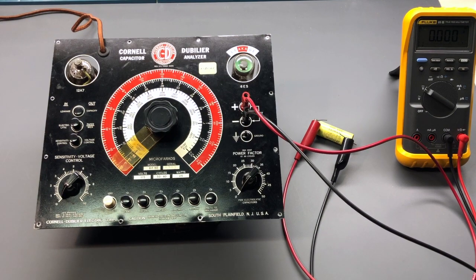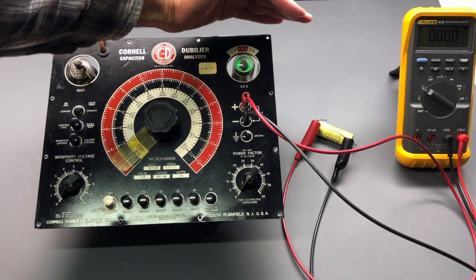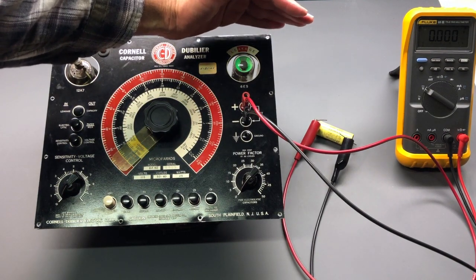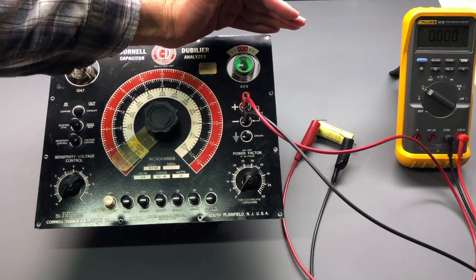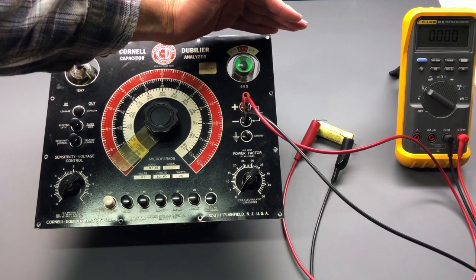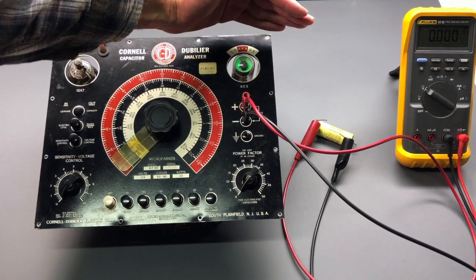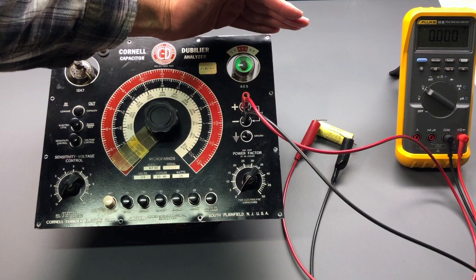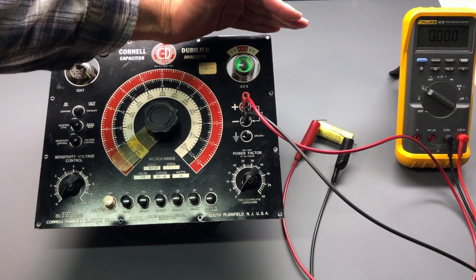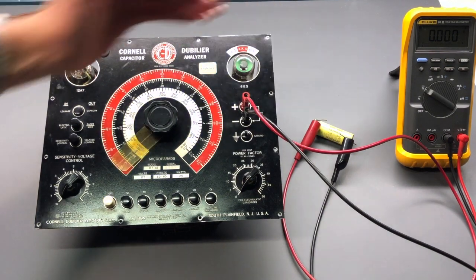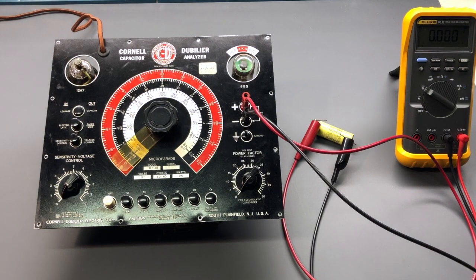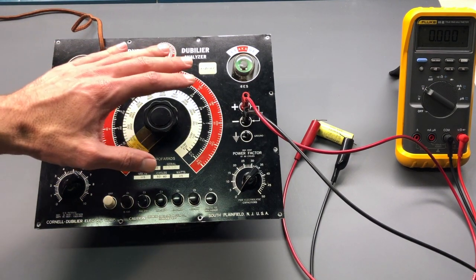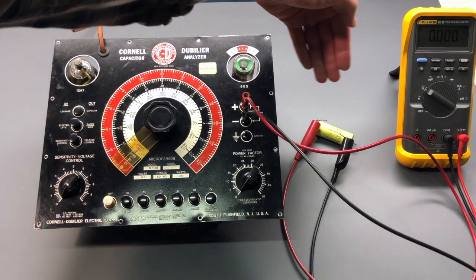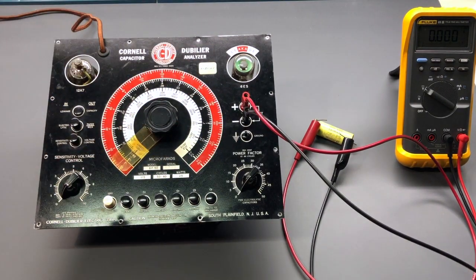Okay, I have the tester connected to a capacitor, and I've turned off some of the overhead lights so that you can see this eye tube glowing, and that's a very good sign that that's turned on. And you can see the wedge or segment in the top is open right now, but we'll watch for activity on that during the leakage test. Now this capacitor is known to be good, but we'll make it leaky and see how this responds for a capacitor that would be leaky, and we can do that by connecting a resistance across that capacitor.